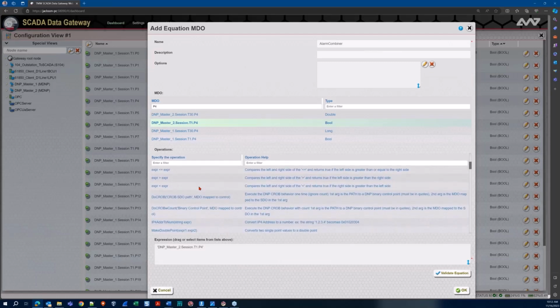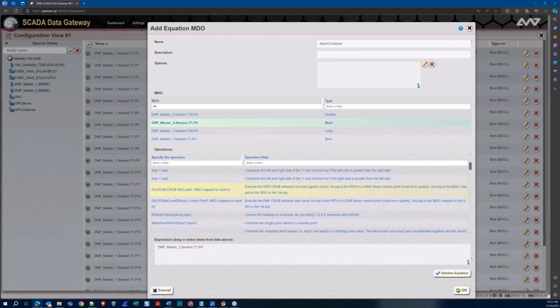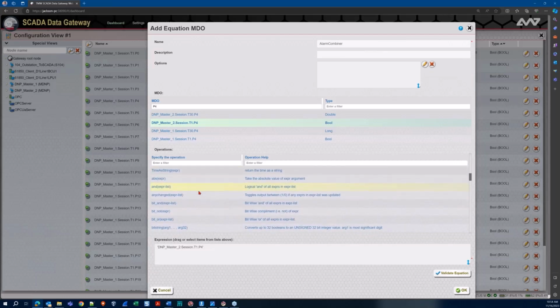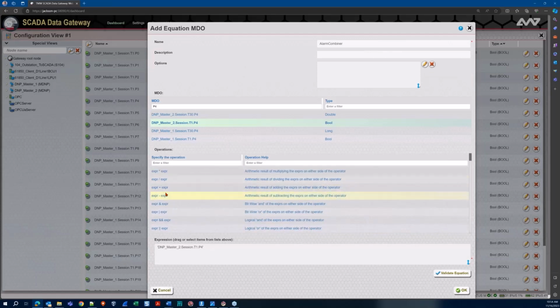This could go anywhere from basic ORing together, like I'm doing today, to some fairly sophisticated control. For now, I'll stick with an OR, this operator, a bitwise OR, and OR it together with the same equivalent alarm in Bay 2, which is DNP Master, Bay 2, T1 P4. I'll OR together with Master 1. So the same point on two different devices from two different bays. If either one of those alarms becomes true, the alarm will become active.